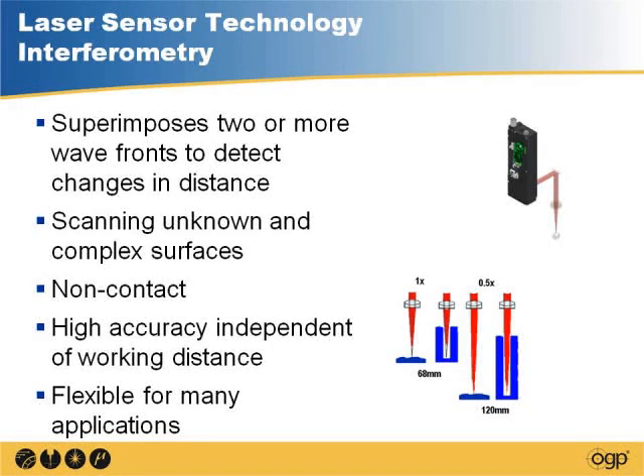The other advantage of it is that it can measure right next to a vertical wall. With triangulation, sometimes if a beam is headed downward and there's some blockage associated with a fixture or the wall on the part, it gets blocked and you're not able to measure right next to the wall. So this comes straight down and straight back up, which is a huge advantage.